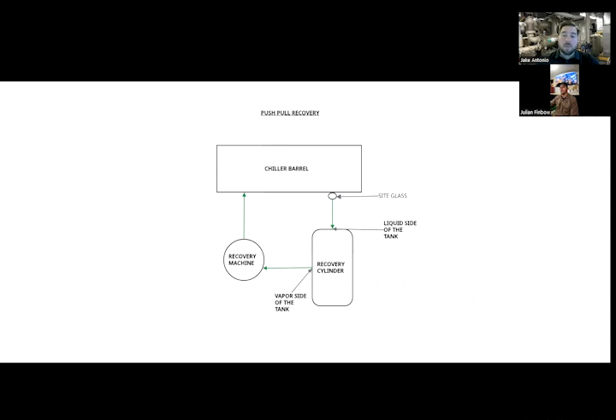So at that point, when all the liquid is in the recovery cylinder, you're going to look at the sight glass and see that the liquid has been moved. It's all been moved into the tank. And at that point, you would close off the liquid side. So that's why it's important to have valves on every hose that you have here so you can valve this off. Or you can use the valve on the chiller itself. So I would close off the liquid side when you get to that portion of it. So I'm just going to kind of show that here.